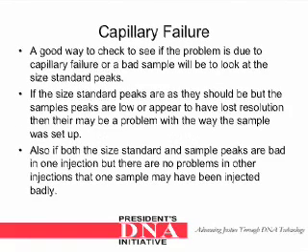A good way to check whether the problem is due to capillary failure or a bad sample is to look at the size standard peaks. If the size standard peaks are as they should be but the sample peaks are low or appear to have lost resolution, then there may be a problem with the way the sample was set up. Also, if both the size standard and sample peaks are bad in one injection but there are no problems in other injections, that one sample may have been injected badly.